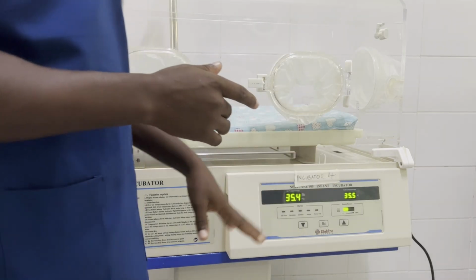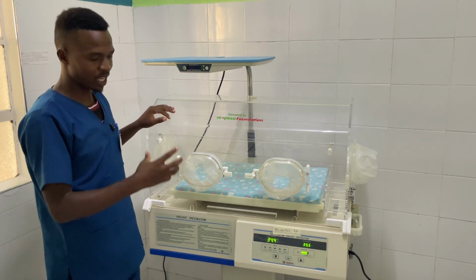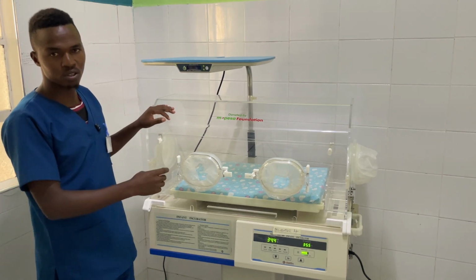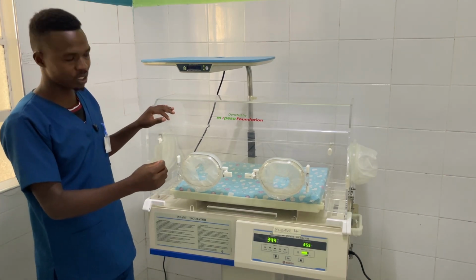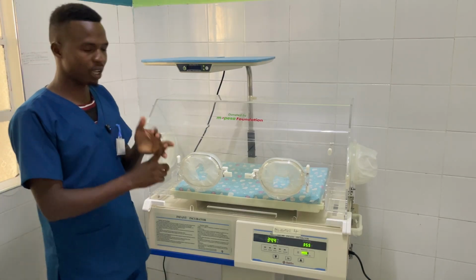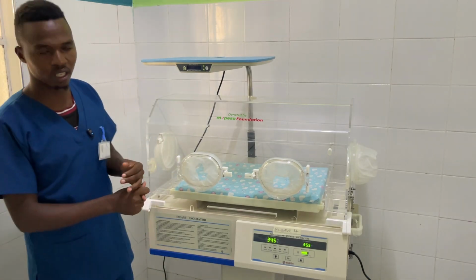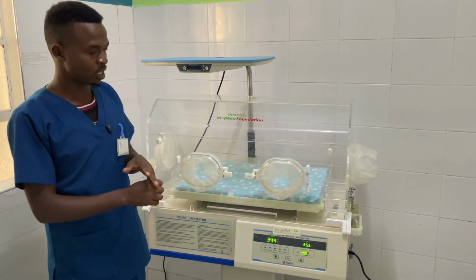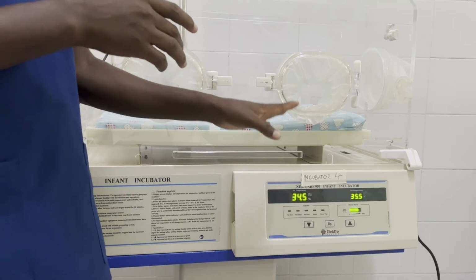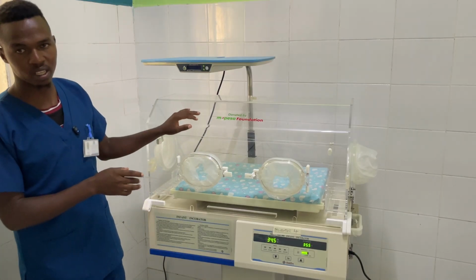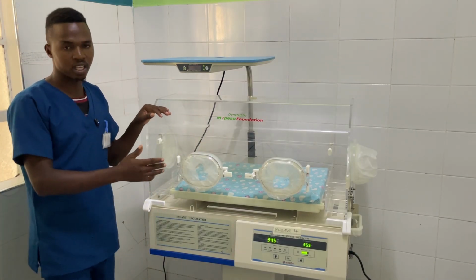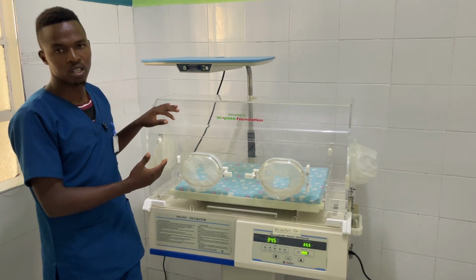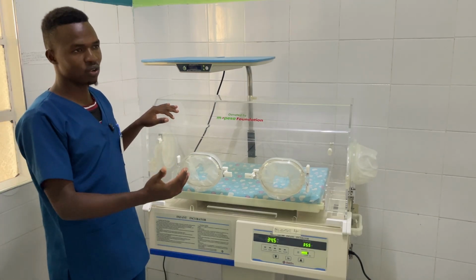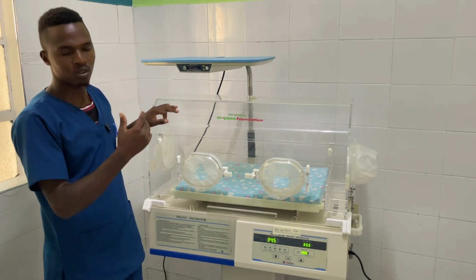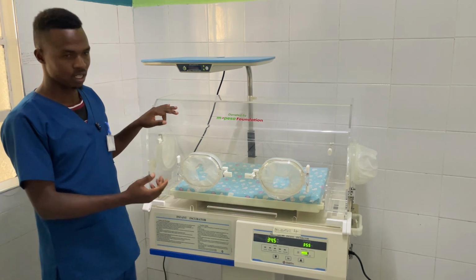Check your incubator. In case it's not working, you can call either the nurse you're working with or the maintenance office. If you have come in and switched on your machine and it's not working, it may have some fault. If you are trying to warm it and the temperatures are not rising, they're still low, know that there is something not working well with your machine. So you have to call the assistants or the qualified nurse for quick assistance.